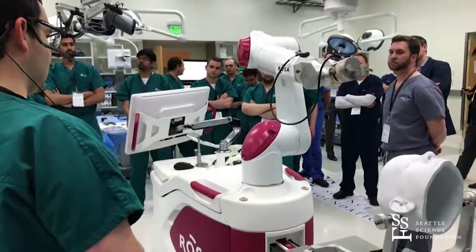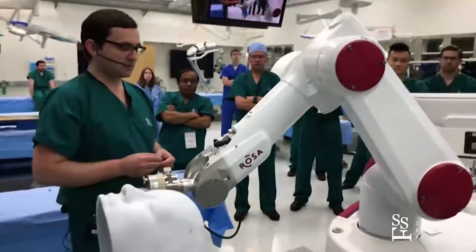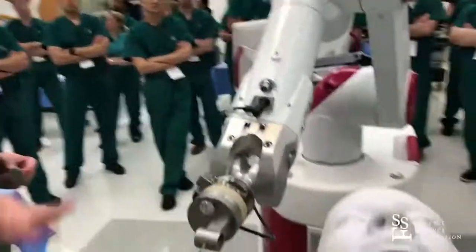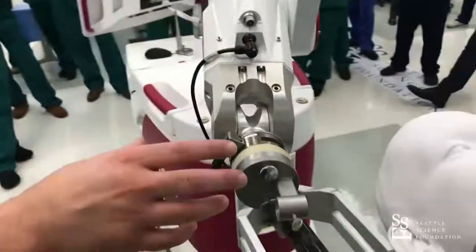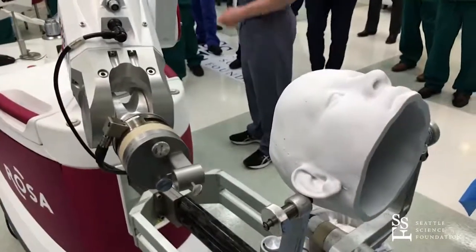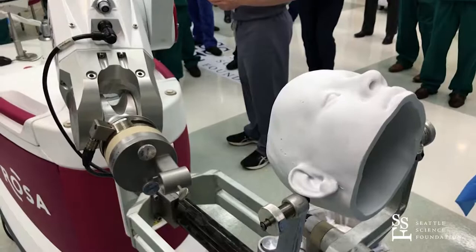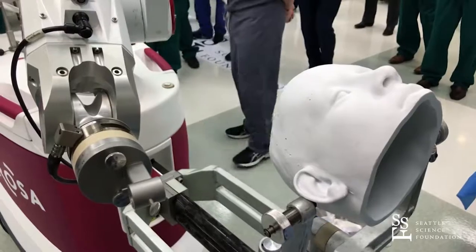And so this is, once again, stereo EEG, and the robots, or at least the robotic arms, really go hand in hand. The advantages for DBS, two leads or a single laser ablation, I'm not sure it's certainly not as compelling, but when you're having to change multiple trajectories, coming in at different trajectories like this, you can't do this with a Leksell unless you put it on sideways. With a CRW, you can maybe have a little bit more freedom, but it can be difficult, and the robots really allow that to be a lot easier.